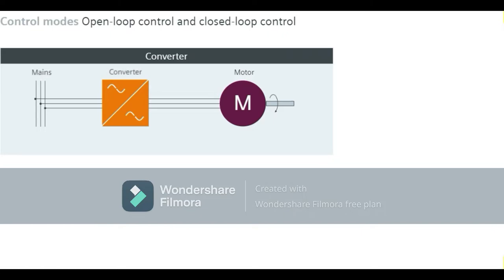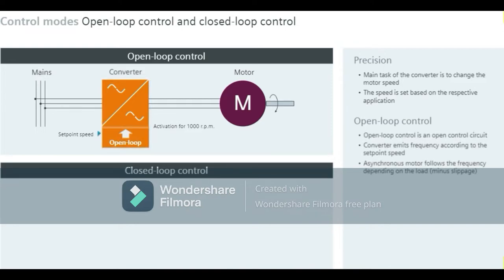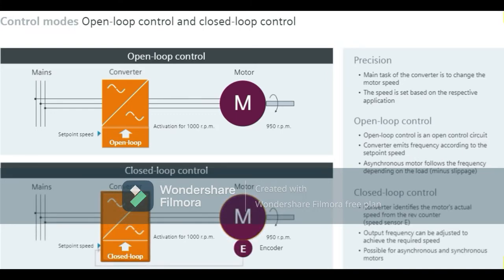The converter's main task is to change the motor speed, which is normally referred to as speed control. The question that often arises is how precisely the speed must be set — this depends on the respective application. In open-loop control, the converter emits a frequency corresponding to the set point value, and the asynchronous motor follows the frequency minus slippage, meaning its speed depends on the load. In closed-loop control, the converter can detect the motor's actual speed using a rotary encoder, also known as a speed sensor, and if necessary adjust its output frequency to maintain the precise desired speed. This function can be used with both asynchronous and synchronous motors.